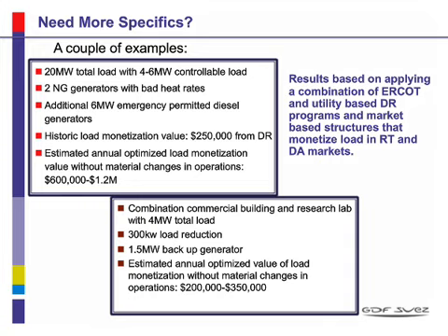I have another customer not represented on this particular slide. It's an industrial facility that's a 24/7 continuous operation, totally distributed, meaning that they don't have one production line that's easy to get at. They have literally hundreds of pieces of small equipment doing assembly. And they looked at that and said, well, there's no way we can harness all this stuff. We said, you don't have to. What we were able to do is find no more than about 300 kW of load that had some flexibility, and primarily through just utility demand management, just managing their utility peaks, we've been able to create in the neighborhood of $150,000 to $200,000 a year in cost reduction for them, which translates to about a 5% overall net reduction in their energy spend.